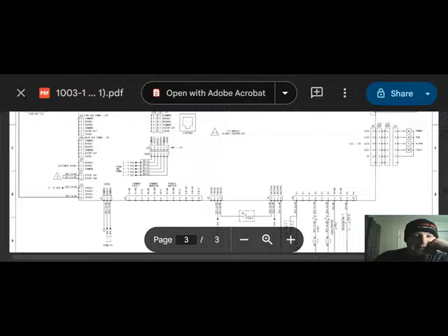And again, it's as wild as your imagination as far as how you use these contacts and what you tie them into. So, biggest thing to remember here is that this is a dry contact. There's no power supplied to these from the machine. You have to bring your own power source. So that pretty well covers the fault contacts and the warning contacts. Like I said, they both basically look the same way. It's just one's triggered by a warning, one's triggered by a fault, and both are tied in however your little heart desires.